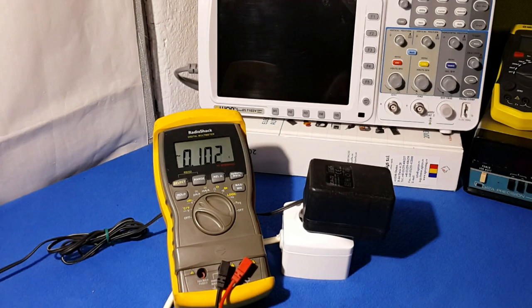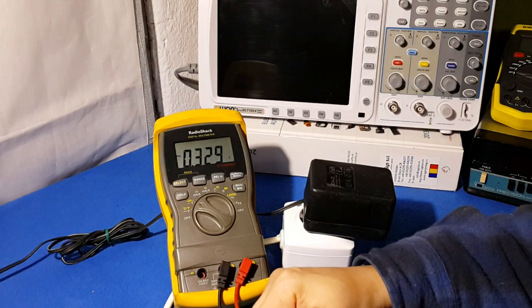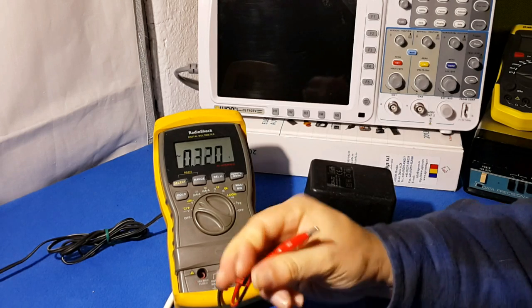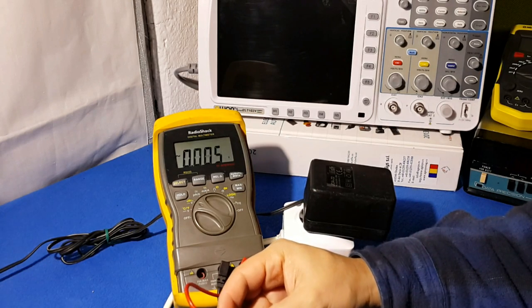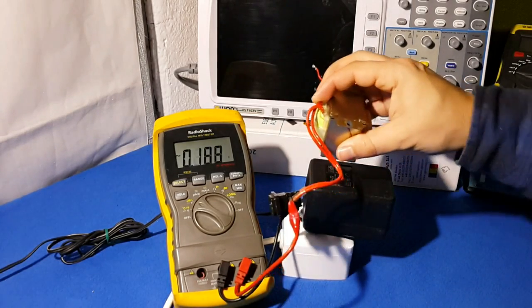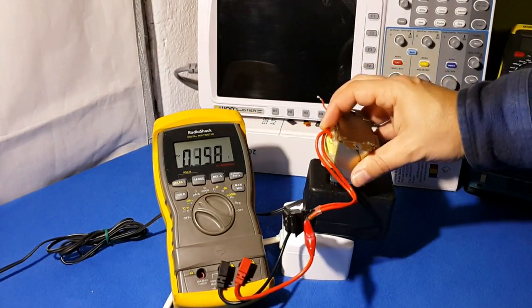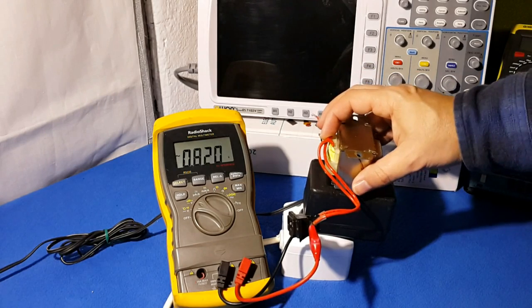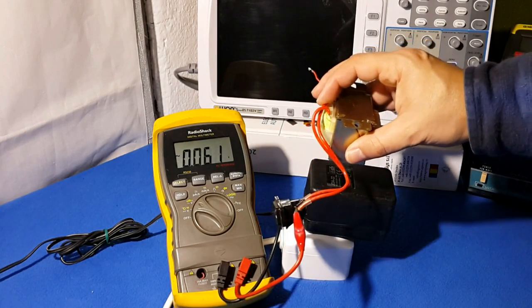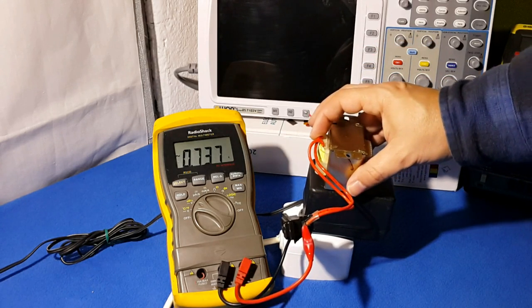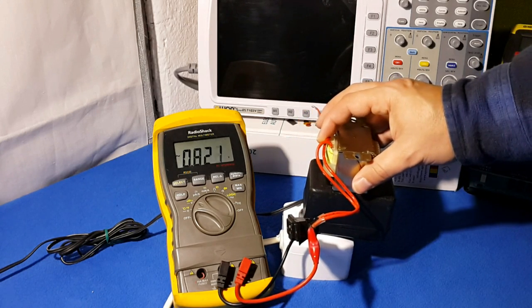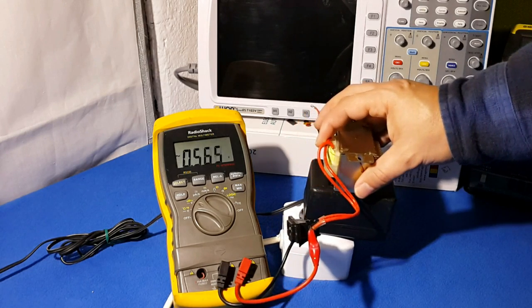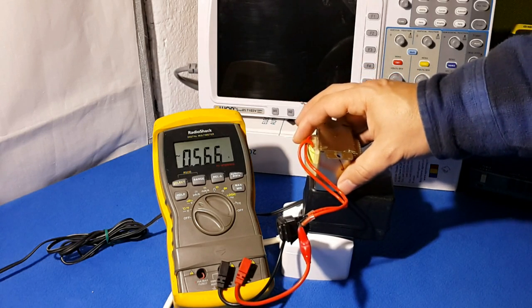Now with a digital multimeter, we are going to use the voltmeter. Let's see what is going on in the primary. Once again, I will get close to the transformer. I get about 800 millivolts. That will be about 40 or less than 40 millivolts is what we are expecting to get in the secondary.